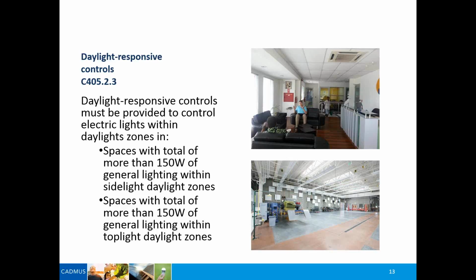In earlier codes, you used to have the option of manual controls in daylight zones, and in the current set of requirements, you are required to put in automatic daylighting controls in daylight zones. A daylit zone, by definition, is essentially this: you've got two types of glass in your building. You have vertical glass, basically windows, which the code refers to as sidelights, and skylights, basically glass in your roof, which the code refers to as toplights. A daylit zone in front of a window is going to be from the surface of the window back 15 feet and then 2 feet on each side of that window.